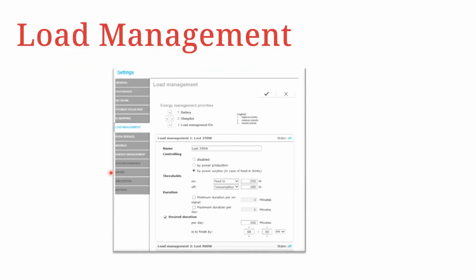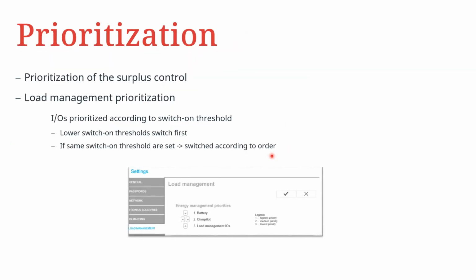So as far as prioritization is concerned, what I should add in addition is that the prioritization will switch on from the lowest threshold to the highest. And if 2 loads have the same switch on threshold, then they will be switched according to how they are listed in that particular prioritization area. So the load that is higher on the list would start first, regardless whether they have the same starting or switching on threshold.